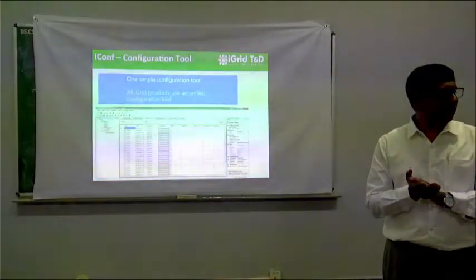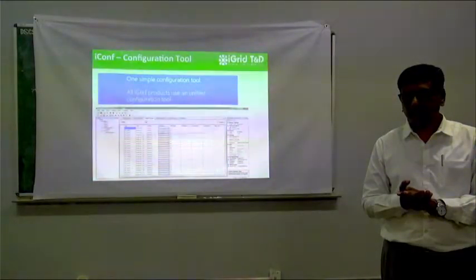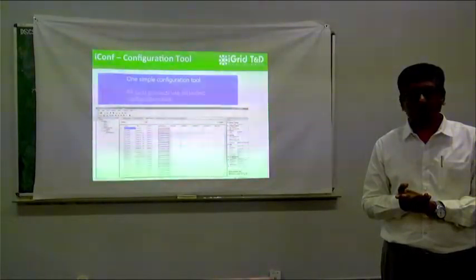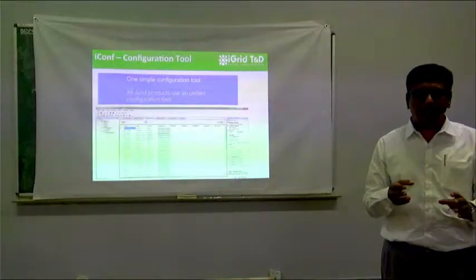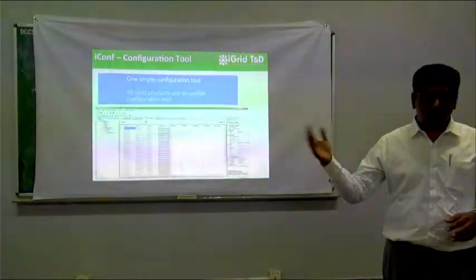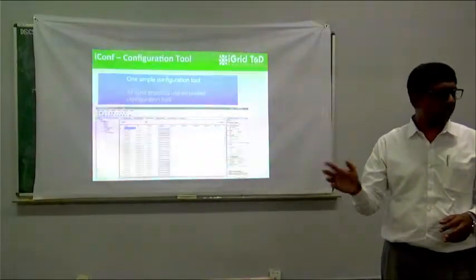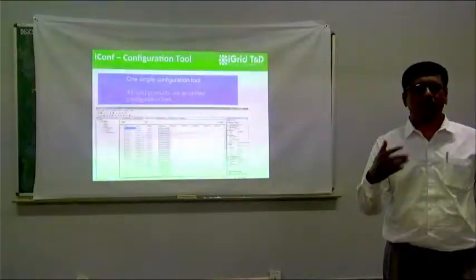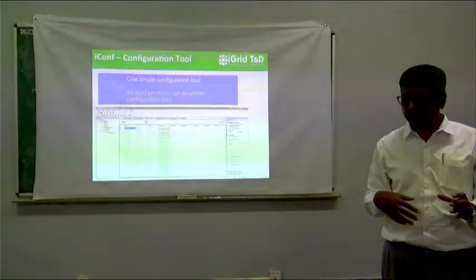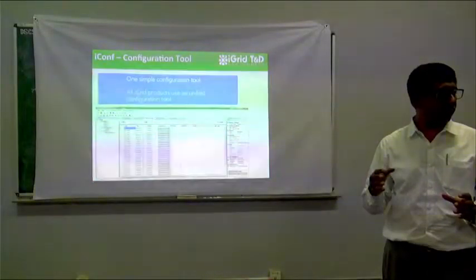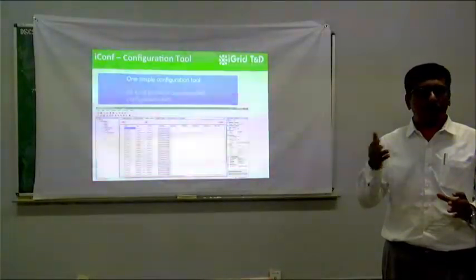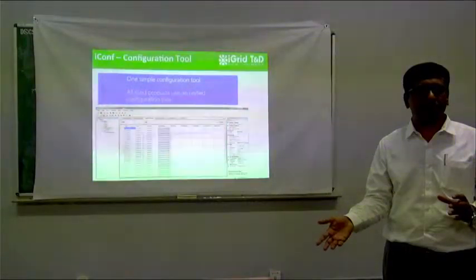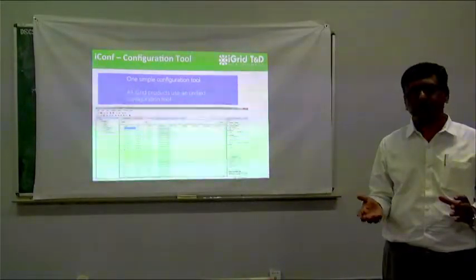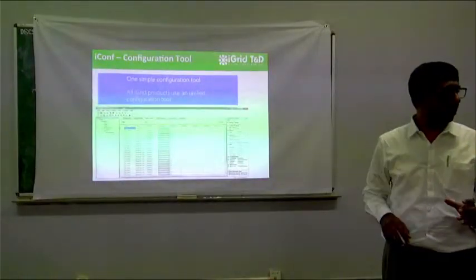Whenever we want to configure these devices, we have a configuration tool called iConf, which my colleague is going to show you. So we have this gateway and our iControl SCADA. We have a lot of devices in the substation, and I need to configure my gateway to read data from all these relays and meters. So I use the iConf configuration tool to add all these devices to my gateway, apply the configuration, and then my gateway starts communicating.